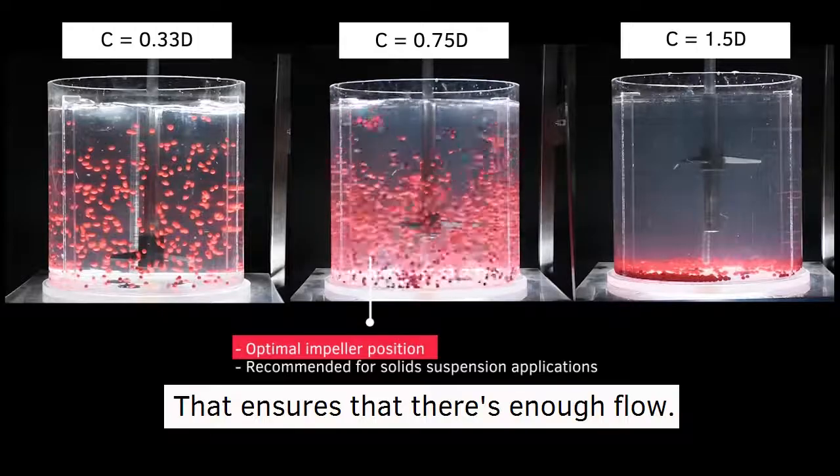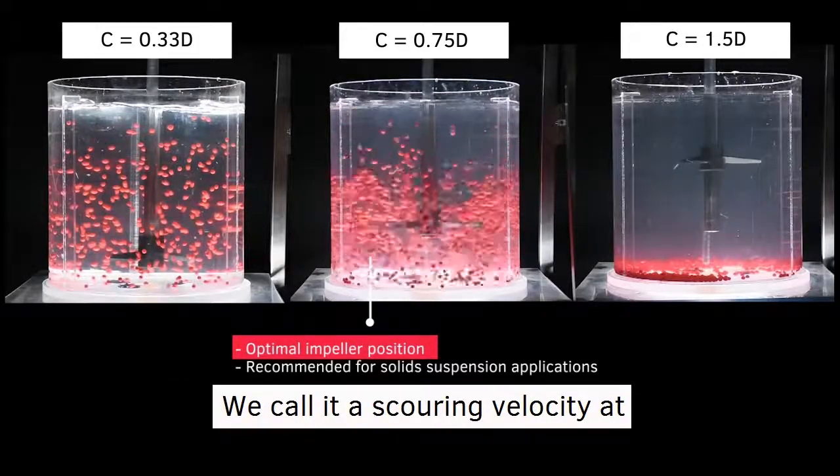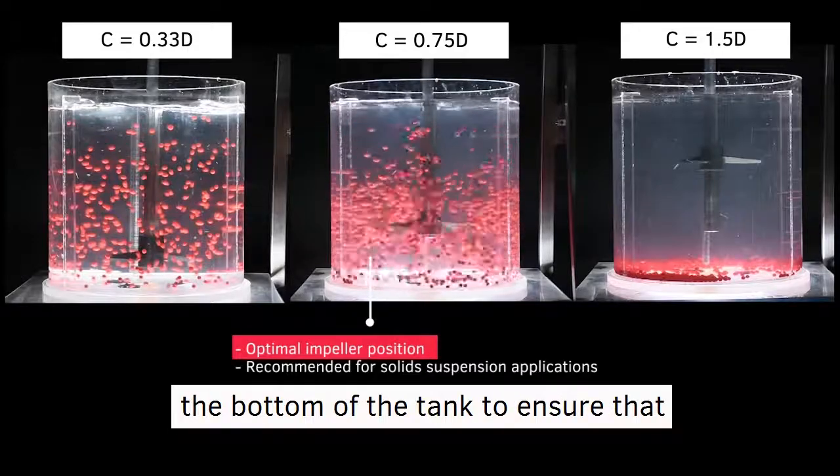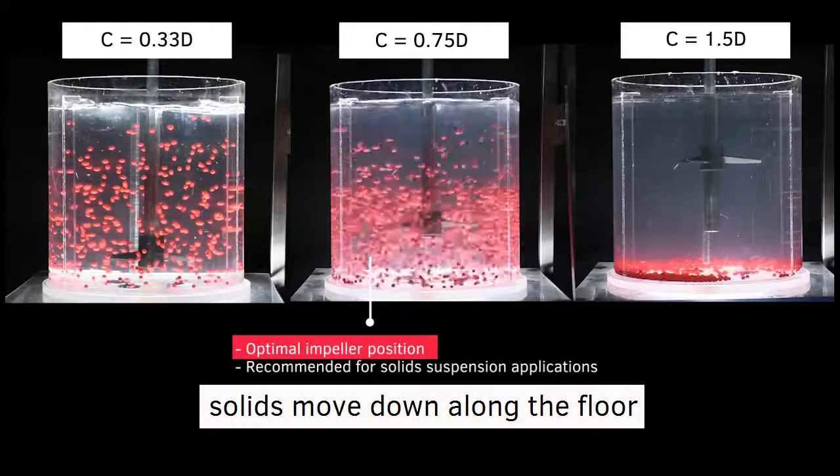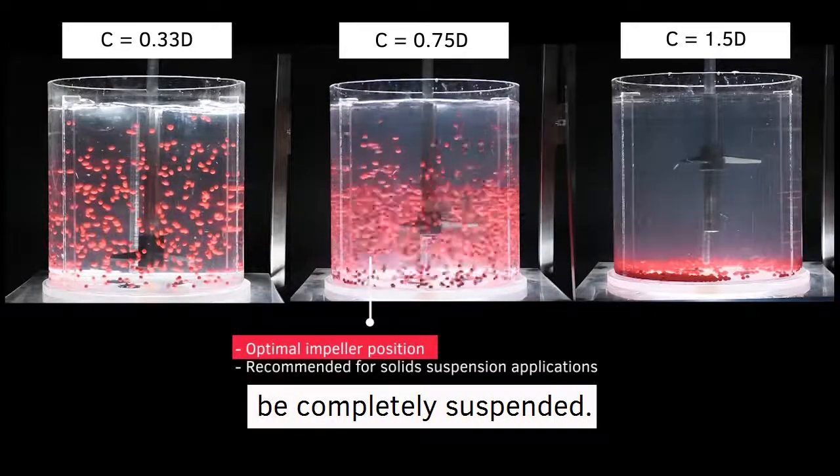This ensures enough flow—what we call scouring velocity—at the bottom of the tank, ensuring that solids move along the floor and up the side of the tank to be completely suspended.